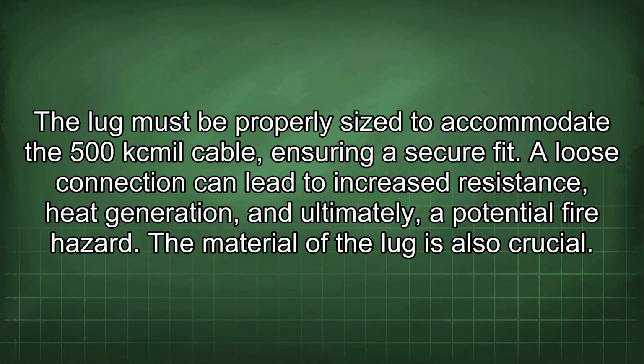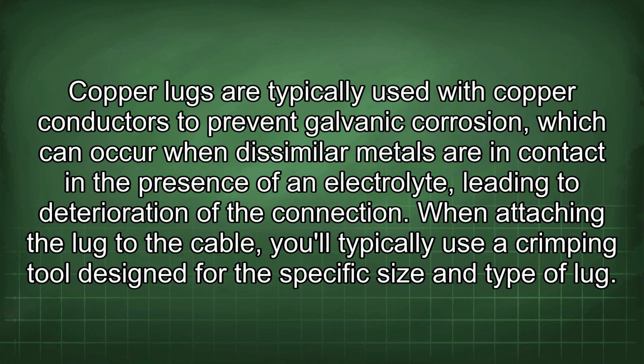The material of the lug is also crucial. Copper lugs are typically used with copper conductors to prevent galvanic corrosion, which can occur when dissimilar metals are in contact in the presence of an electrolyte, leading to deterioration of the connection.